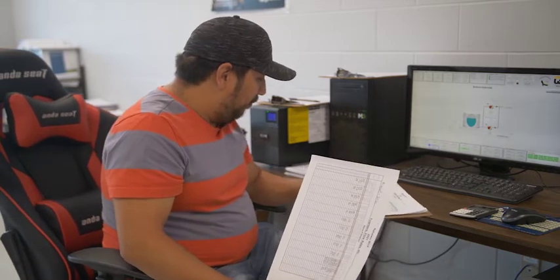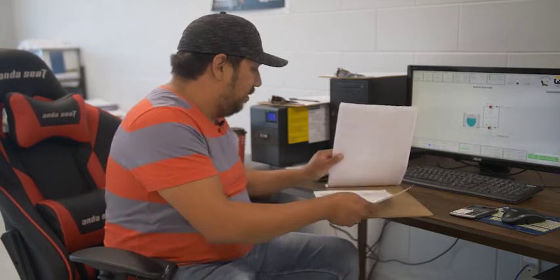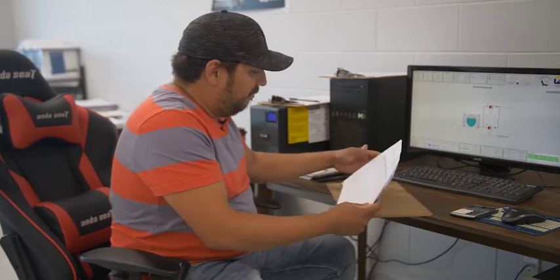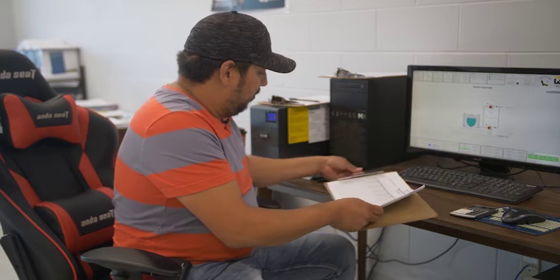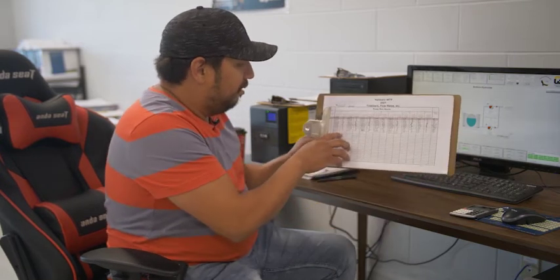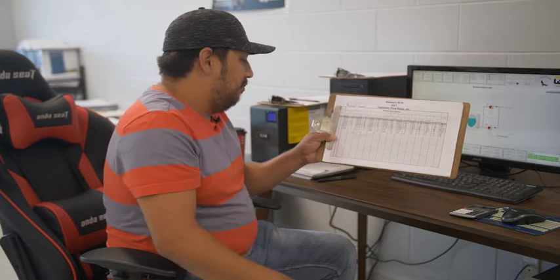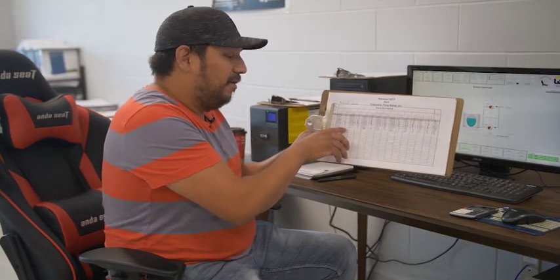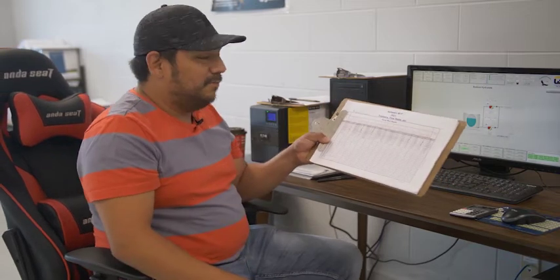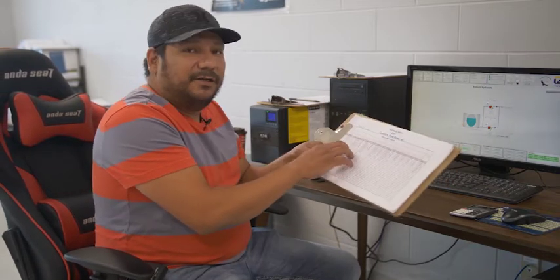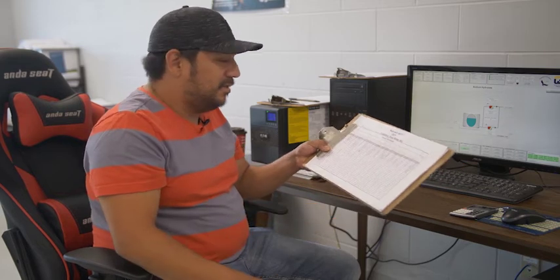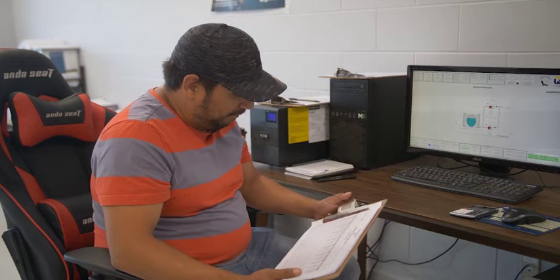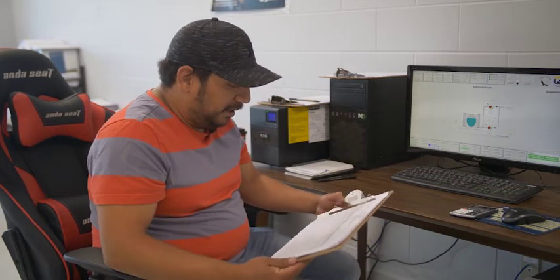Same thing with our pump run hours. If we notice one pump has been running steady when it shouldn't have been, then we know there's an issue. If you notice here, the raw water pumps are intermittent, anywhere from 19 hours a day to 3 hours a day, 5 hours a day, which is the weekend, which is normal. 19 hours a day is probably our Tuesday last week, which is the highest demand day, where the water trucks are running constantly. So our treatment unit is constantly trying to keep up on that day.